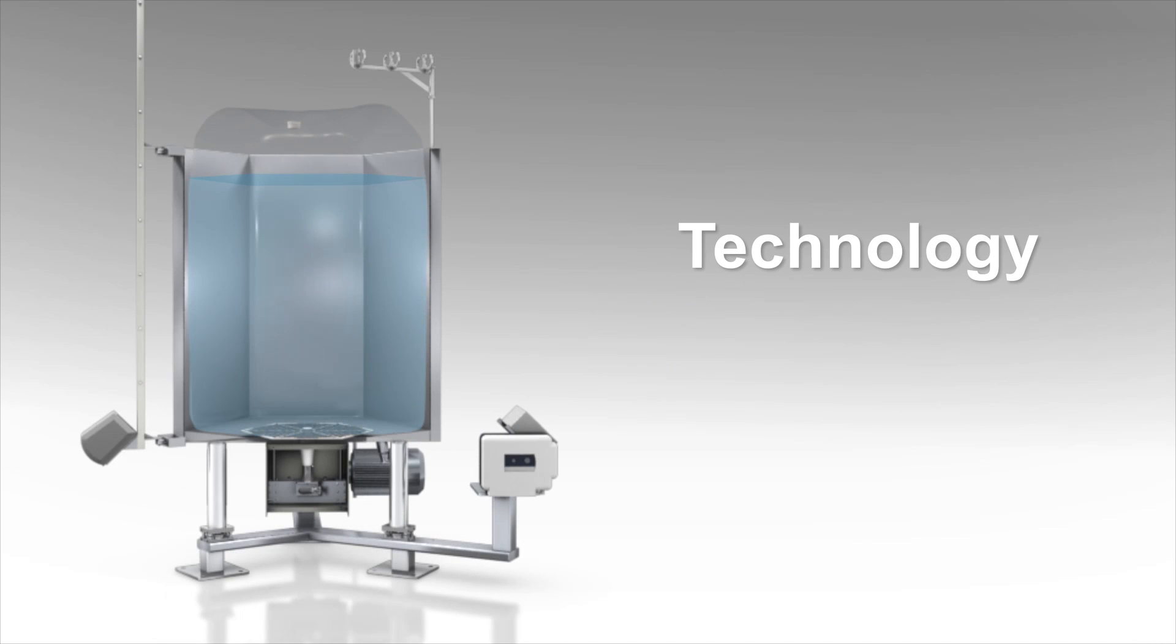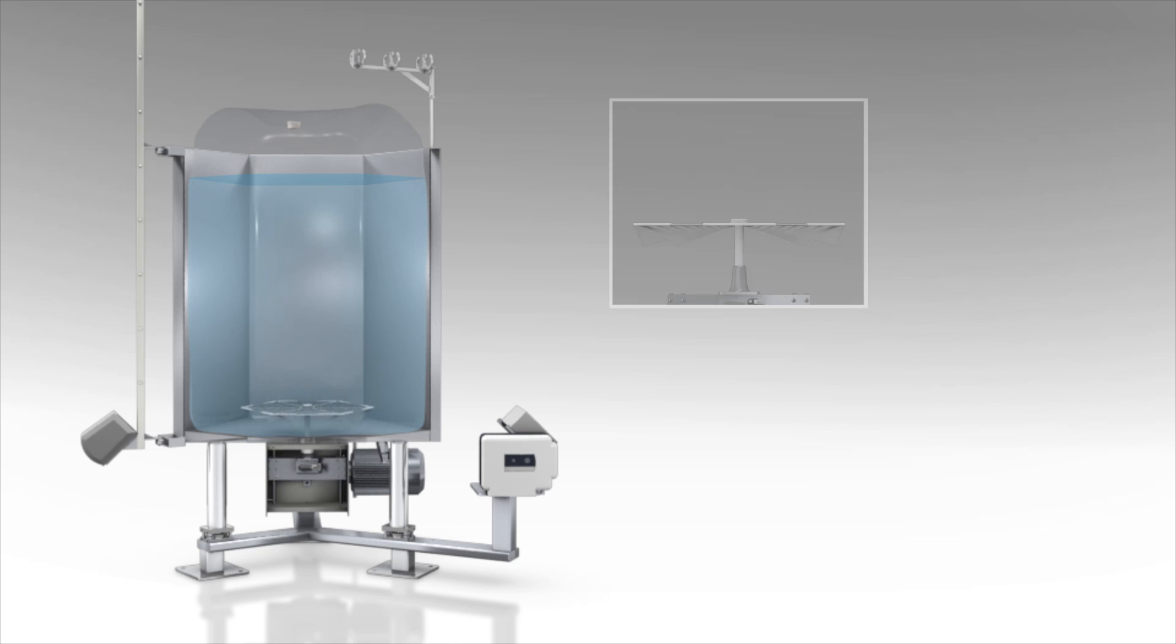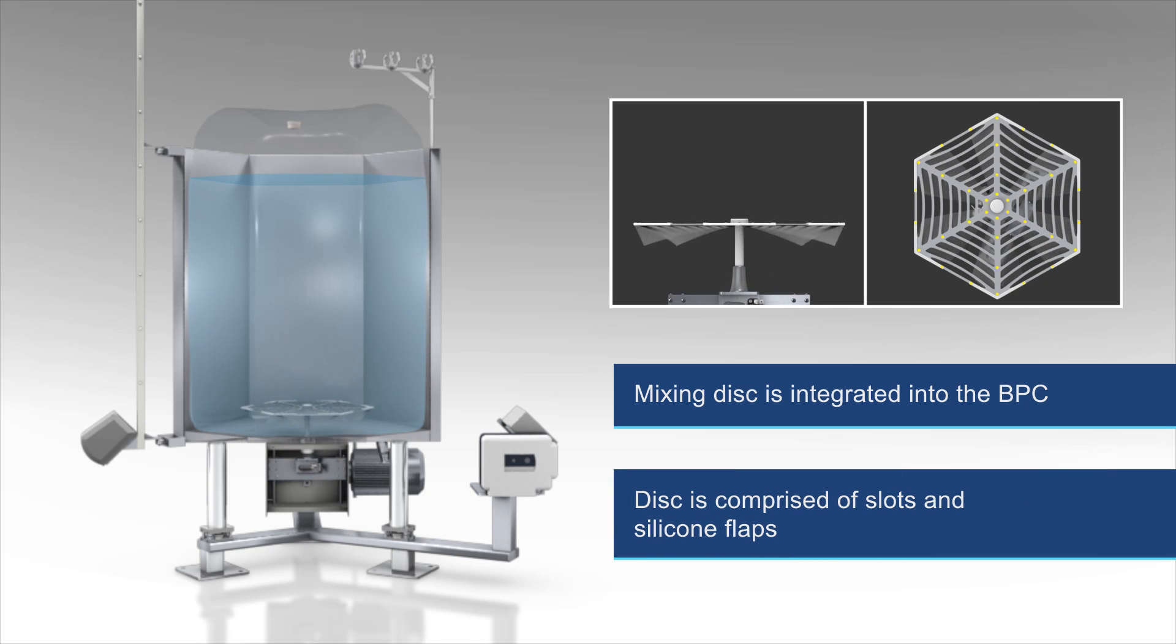The Impulse single-use mixing system's technology is based on a reciprocating motion created by a vertically moving mixing disk. The mixing disk, an integrated part of the bioprocess container, or BPC, is designed with multiple slots and silicone flaps.